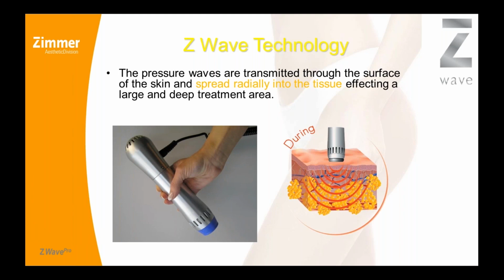There are 2 handpieces on each device, and they are available in 2 different sizes. The smaller handpiece will only be used on small treatment areas, such as the submental area post CoolMini. You will usually be using that larger handpiece. This large tip makes treatment fast, delivers more energy so that it is able to penetrate deep into the fat tissue, and therefore avoiding dermal complications such as bruising.